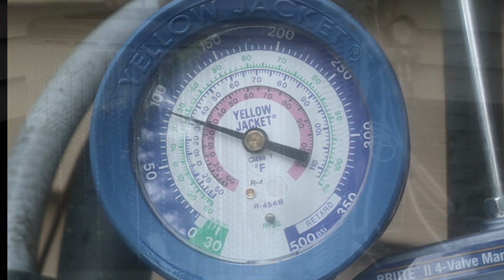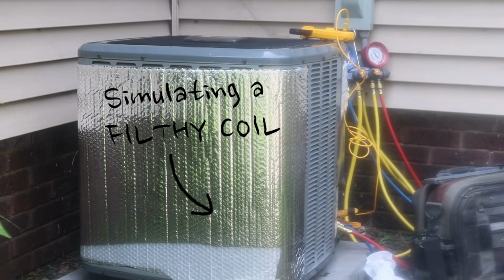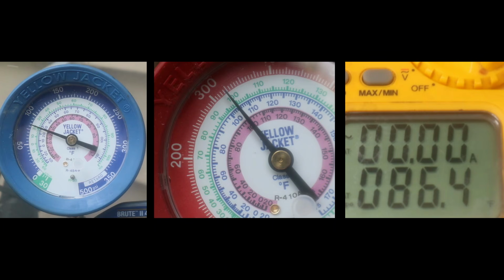Now the problem I created was that I cut off airflow to the condensing unit. As technicians, we're usually not fortunate enough to walk up and actually watch all this happening. We just end up with the end results. We have a low suction pressure, head pressure is a little bit high, maybe even normal, and our subcooling has increased well beyond what it's rated to be.